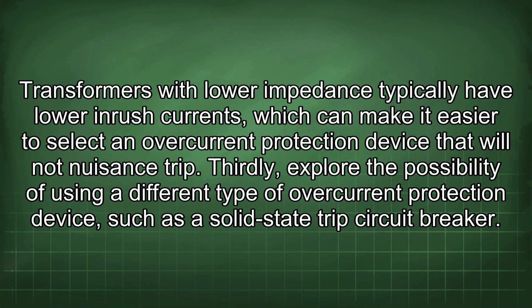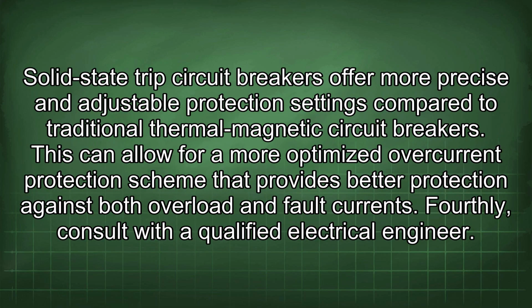Transformers with lower impedance typically have lower inrush currents, which can make it easier to select an overcurrent protection device that will not nuisance trip. Thirdly, explore the possibility of using a different type of overcurrent protection device, such as a solid-state trip circuit breaker. Solid-state trip circuit breakers offer more precise and adjustable protection settings compared to traditional thermal magnetic circuit breakers. This can allow for a more optimized overcurrent protection scheme that provides better protection against both overload and fault currents.